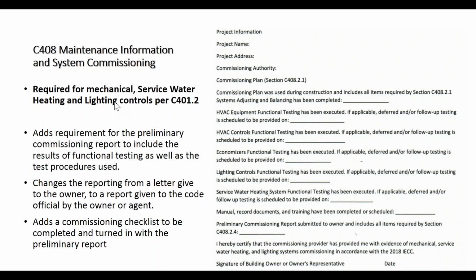Right? So because commissioning applies to mechanical, lighting, and water heating, they just said in 401.2, right up front, in the very front of the chapter, where it says, here's the paths that are available to you. Under each of those paths, if you choose prescriptive or performance, whatever, you have to do commissioning. It tells you that up there. So that is moved up there. So don't think you don't have to do it.